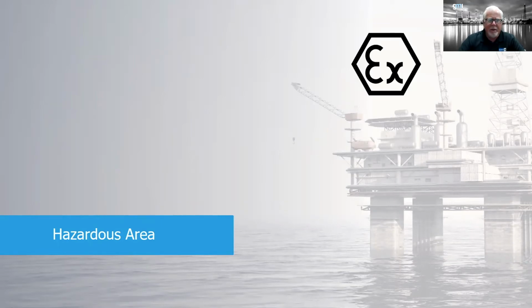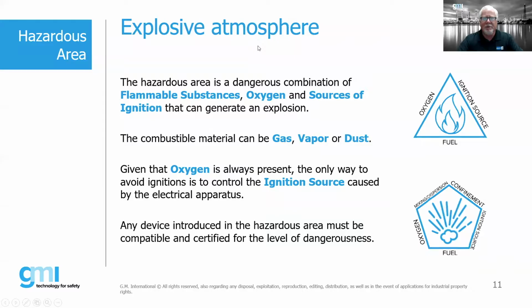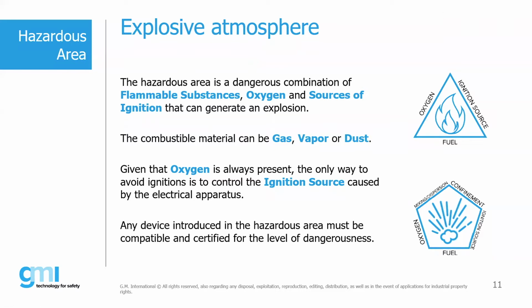But let's get going. So, hazardous areas. Let's see if I can move my screen here. There we go. So, an explosive atmosphere. Again, this should all be basically repetitive for you, but just as a primer, a hazardous area is a dangerous combination of flammable substances, oxygen, and sources of ignition. The flammable substances can be either gas, vapor, or dust. Oxygen is always present. The only way to avoid ignition is to control the ignition sources caused by the electrical apparatus.